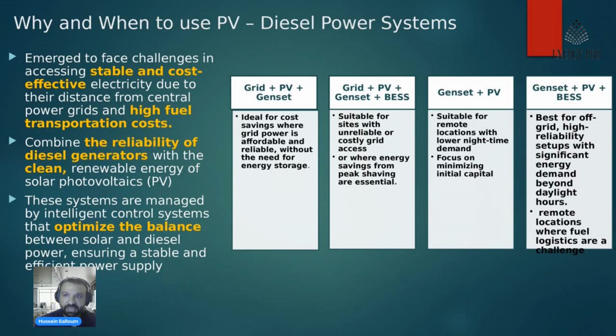However, in case we have a night load, it's recommended that we use a generator with PV and a battery energy storage system, because we can use solar power to charge the batteries during the day and shift to battery operation during the night, saving on generator diesel.